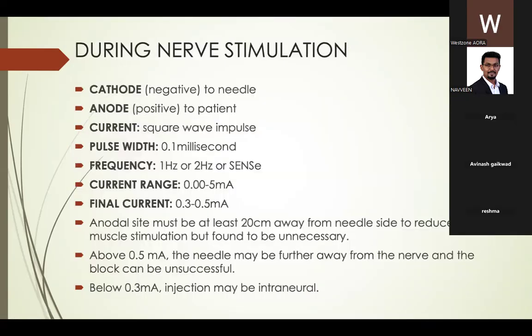So during a nerve stimulation, we need a cathode which is negative to the needle, or the black to the needle, which is universal code, and an anode which is positive to the patient, or the red. And the current must be a square wave impulse. The pulse width should be 0.1 millisecond. The frequency can be set according to 1 hertz, 2 hertz, or SENSe. The current range will start from 0 to 5 milliamperes. So we can start at an initial current of 1 to 2 milliamperes depending on the patient and the site of nerve block we are offering, to a final current of 0.3 to 0.5 milliamperes. And beyond this, less than 0.3, it becomes intraneural.